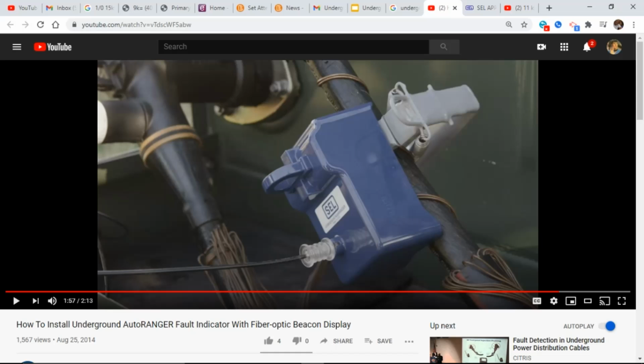Fault current is going to travel one direction, then it's going to travel the other direction going into ground, and it's going to cancel itself. So you're not going to get a true reading off the fault indicator. And I'll go to Paint in just a moment to show you what's going on.